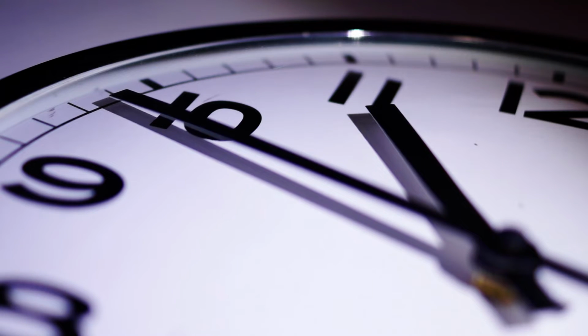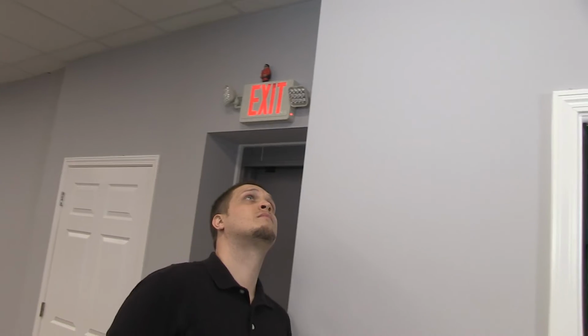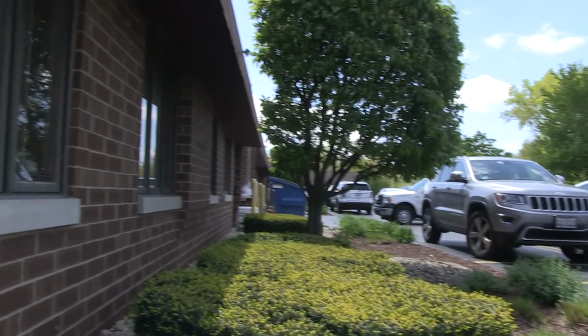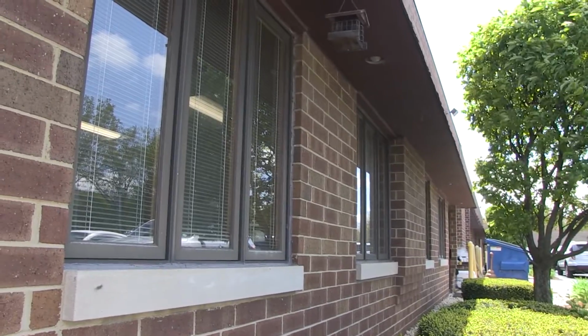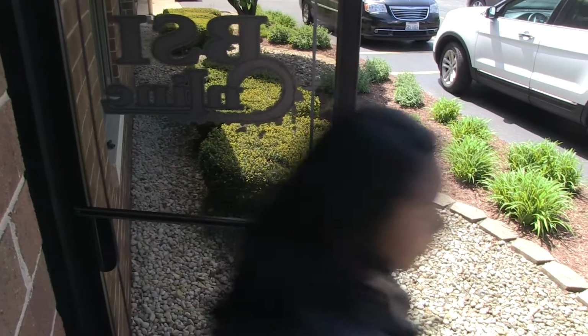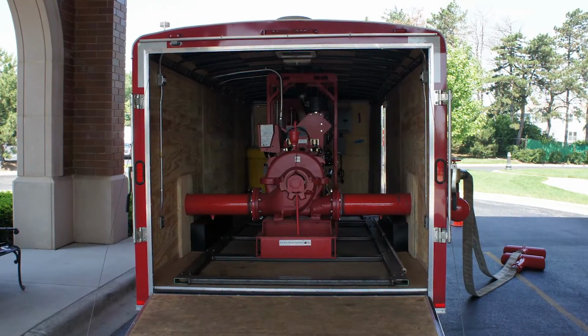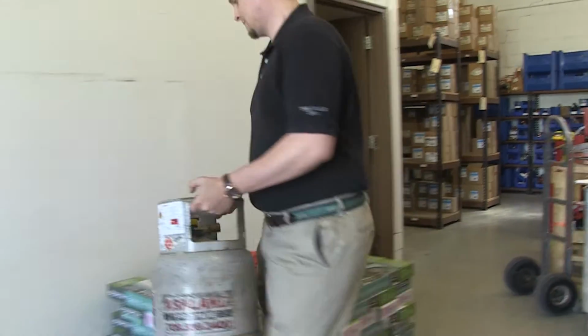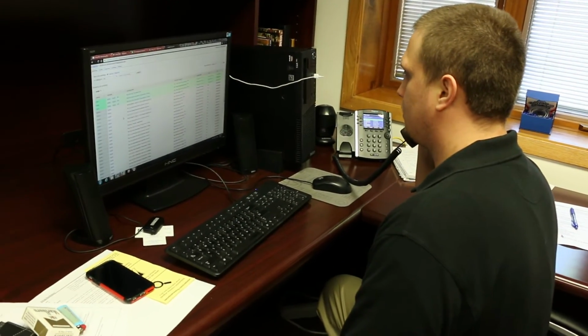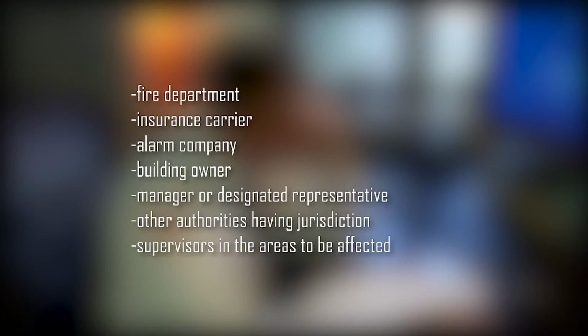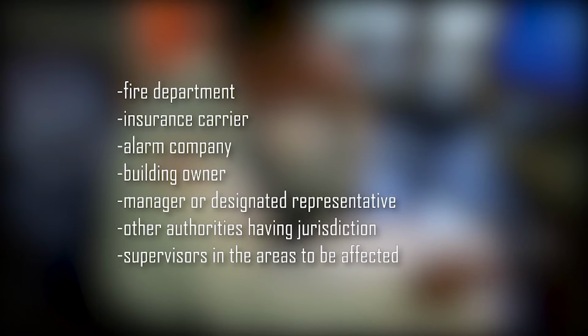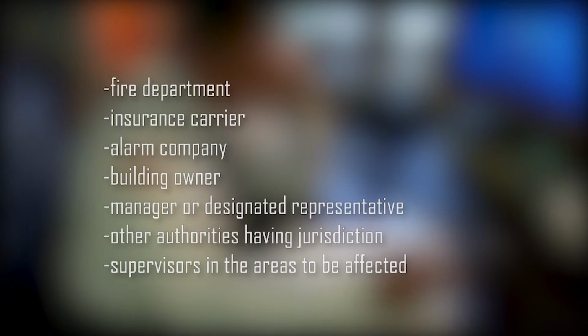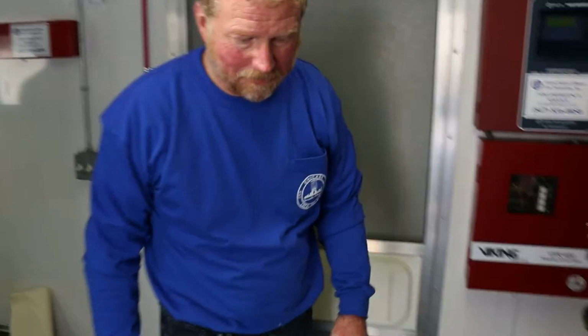1. The extent and expected duration of the impairment have been determined. 2. The areas or buildings involved have been inspected and the increased risks determined. 3. Recommendations to mitigate any increased risks have been submitted to the building owner or manager or designated representative. 4. If the system has been out of service for more than 10 hours in a 24-hour period, one of the following has been implemented: evacuation of the building or affected portion, an approved fire watch, a temporary water supply, or elimination of potential ignition sources and limiting the amount of fuel available for a fire. 5. The following groups and people have been notified: fire department, insurance carrier, alarm company, building owner, manager or designated representative, other authorities having jurisdiction, and supervisors in the areas to be affected. 6. The tag impairment system has been implemented. And 7. All necessary tools and materials have been assembled on the impairment site.